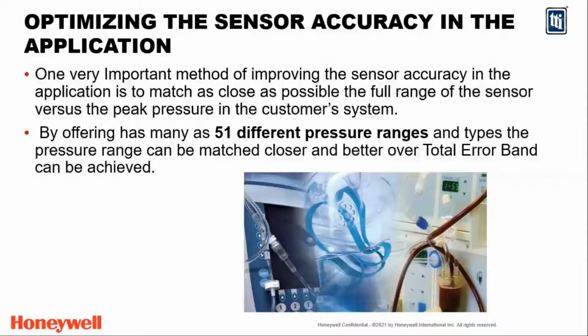If you only require 0.7 psi, you don't want a 5 psi or 15 psi sensor. You want a 1 psi, or maybe even a 160 millibar, something matched much closer to your usage range. By matching it closer, you're going to have a much better total error band in the sensor, and a much better overall error band in your overall assembly and equipment.